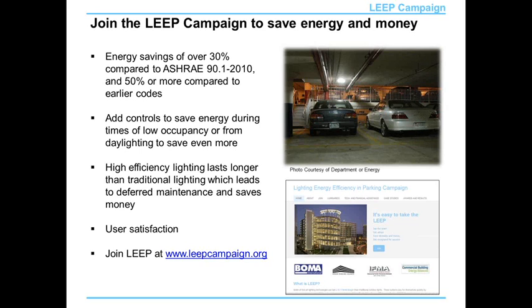The target is 30% compared to ASHRAE Standard 90.1 2010, which actually translates to — can be more than 50% compared to earlier codes, earlier versions of Standard 90, IECC, or Title 24. The exact values differ by what type of parking space you're in, whether it's a parking lot or a parking structure, but that's a pretty good guideline of what the values look like.